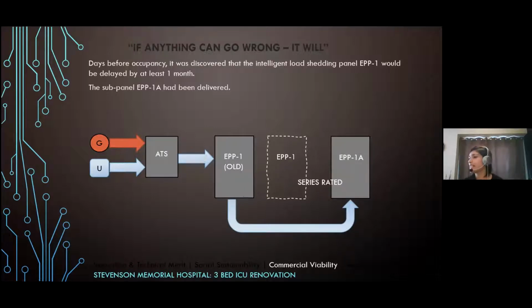It means that in the case that we have the worst possible short circuit fault in our system, these two panels would only be able to safely interrupt that worst possible fault if they're working together. On its own, EPP1A was not rated to interrupt the worst possible short circuit that our system could encounter. So it wasn't safe. So we had to scratch our heads and figure out what else could we do in order to get this ICU operational.